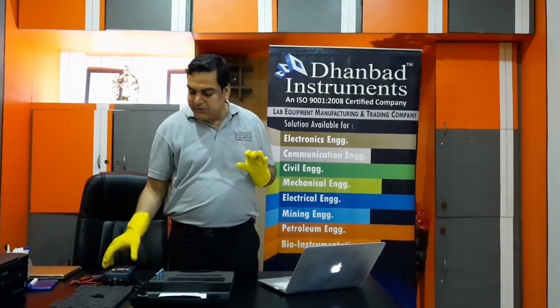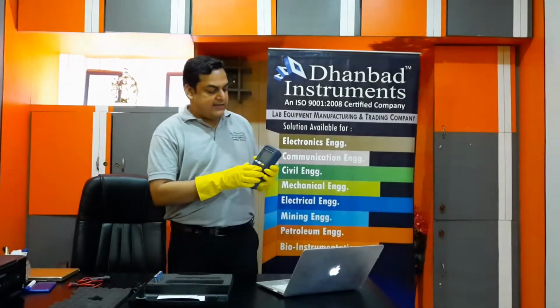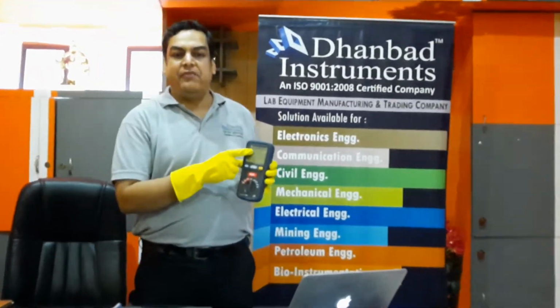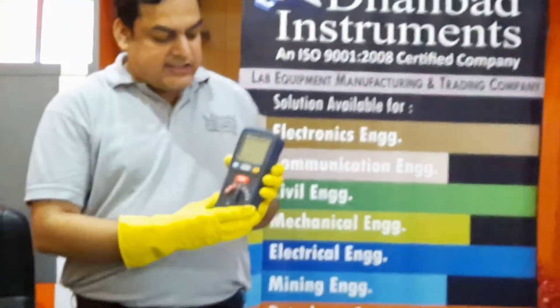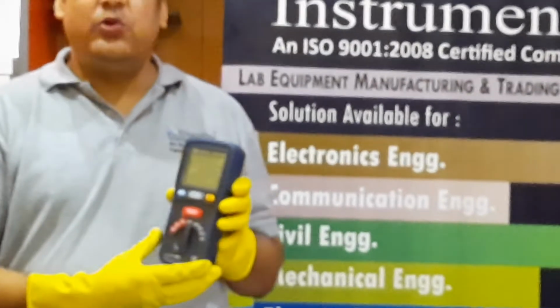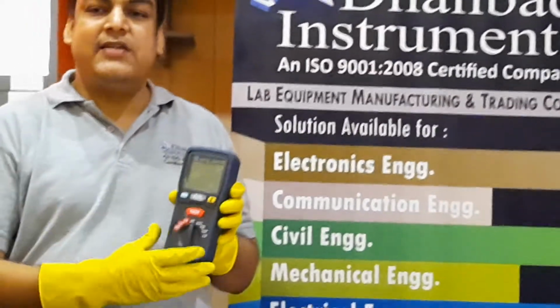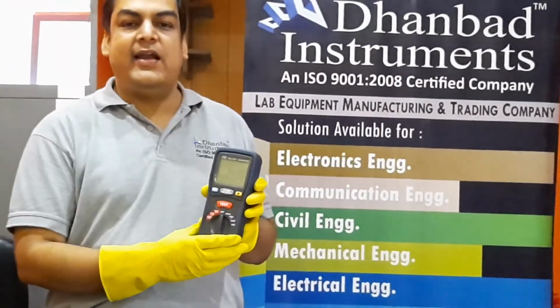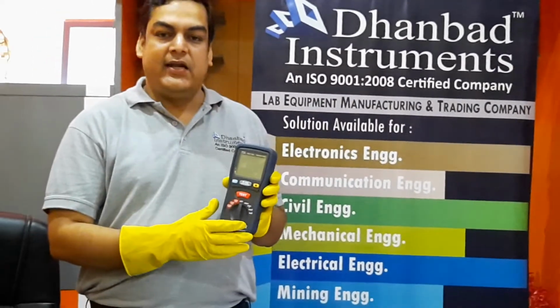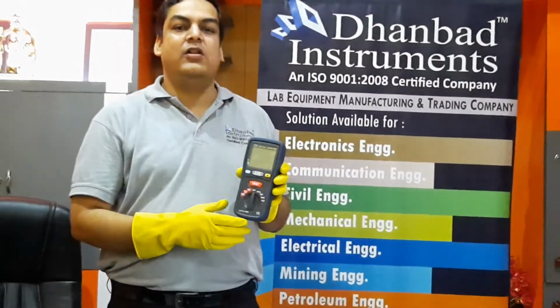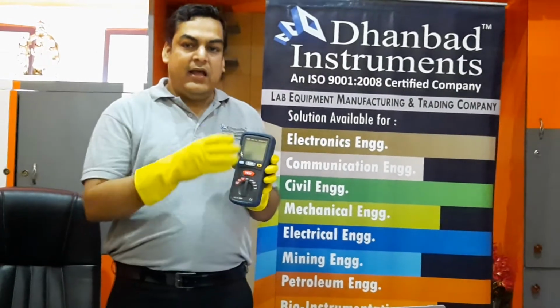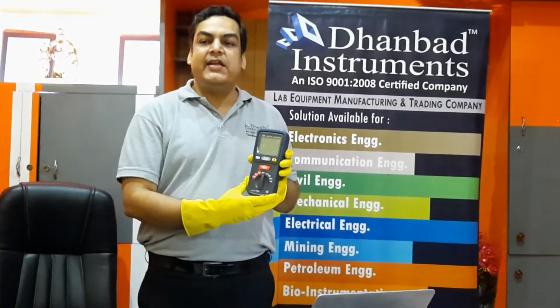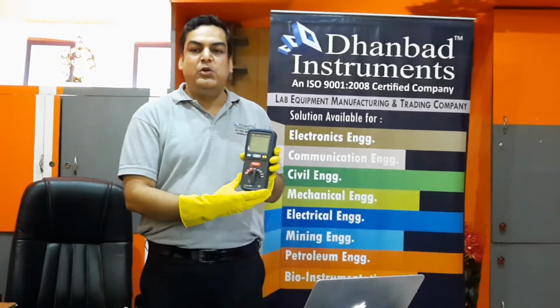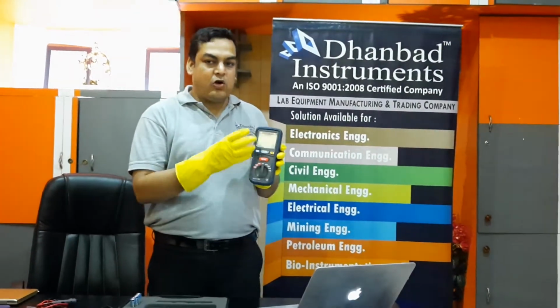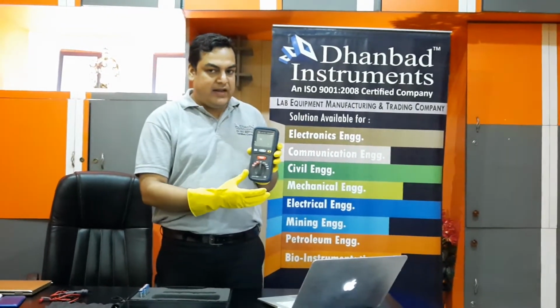So I am coming back to the main instrument, the PC-IT55. This is an instrument used to determine insulation resistance, alternating current, continuous current, and it is used to test all these parameters. This determines insulation resistance up to a maximum of 2000 mega ohm for auxiliary voltage of 250, 500 and 1000 volts.